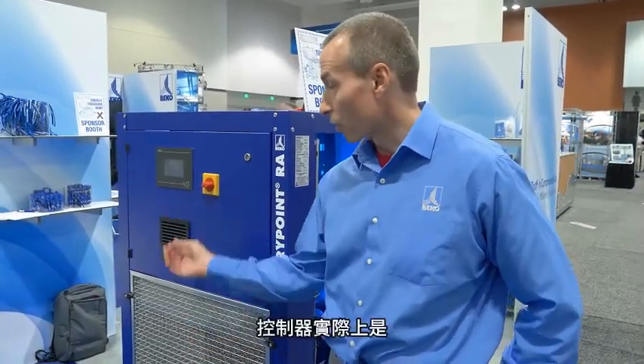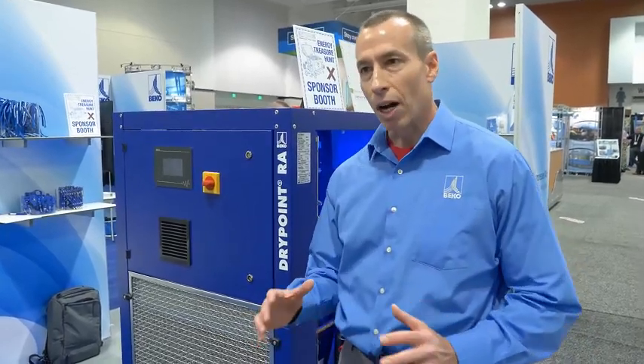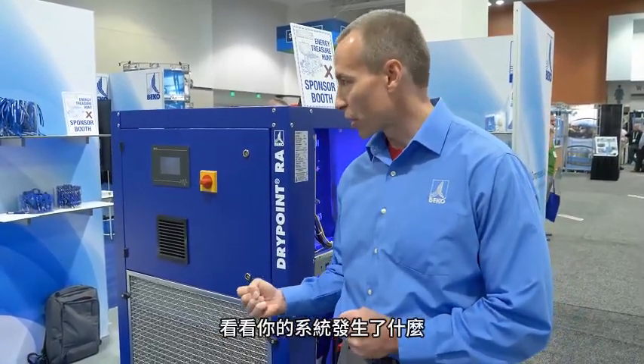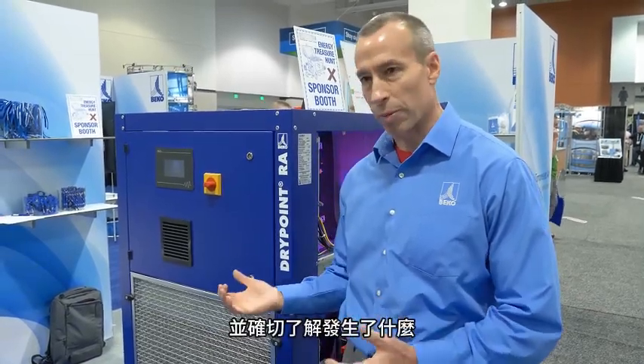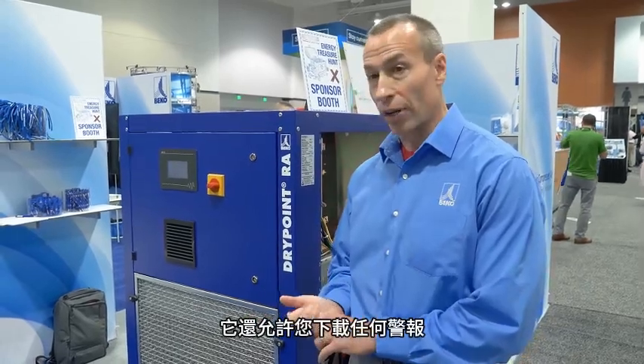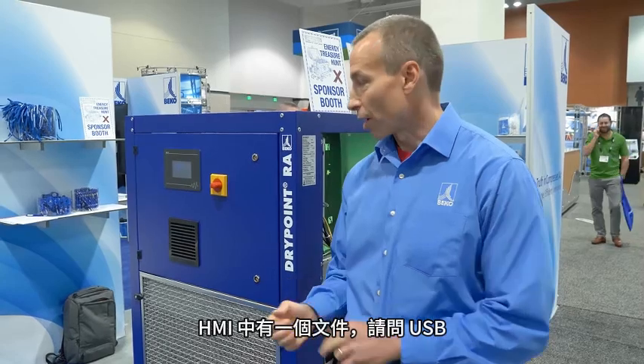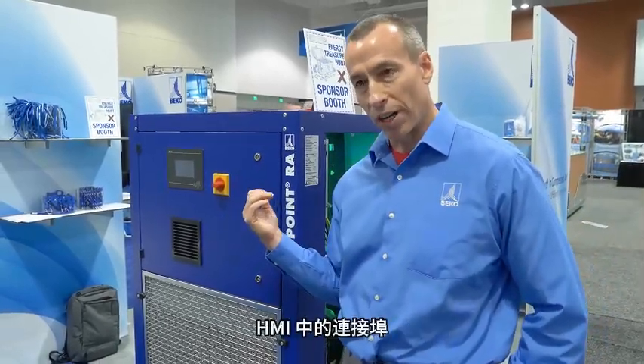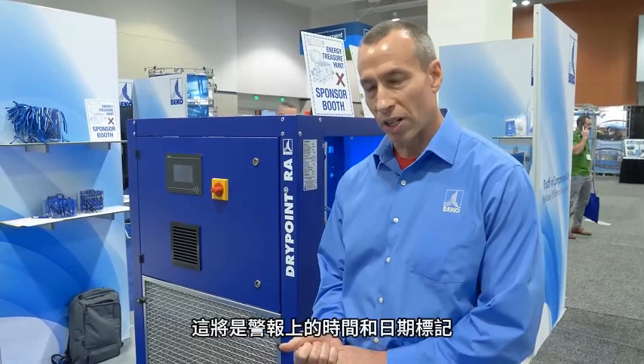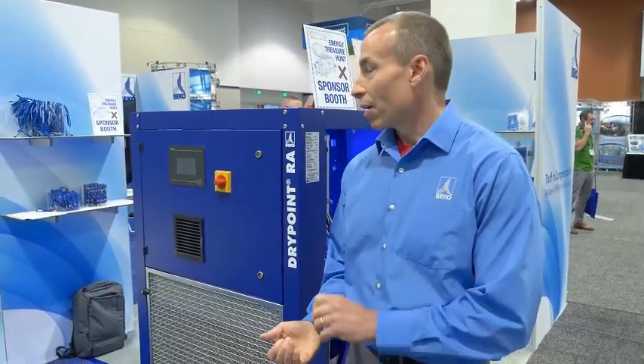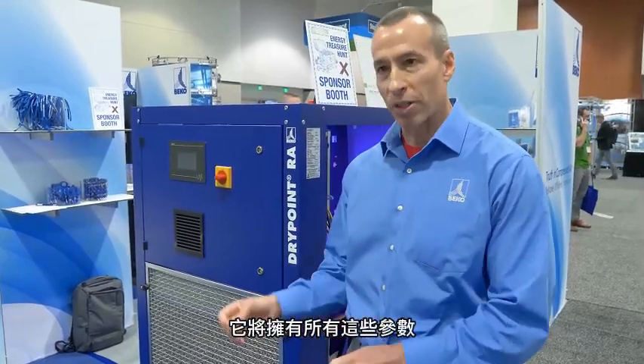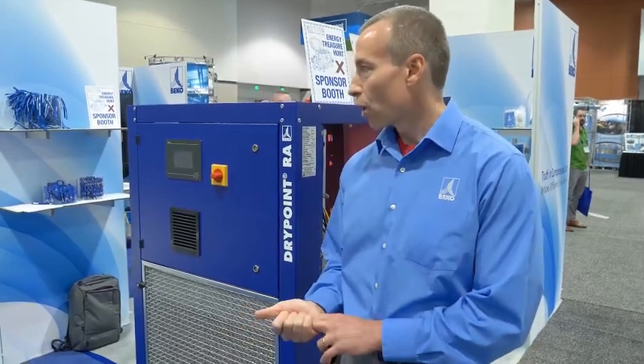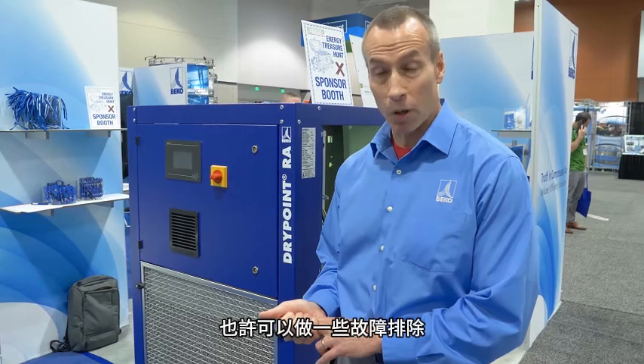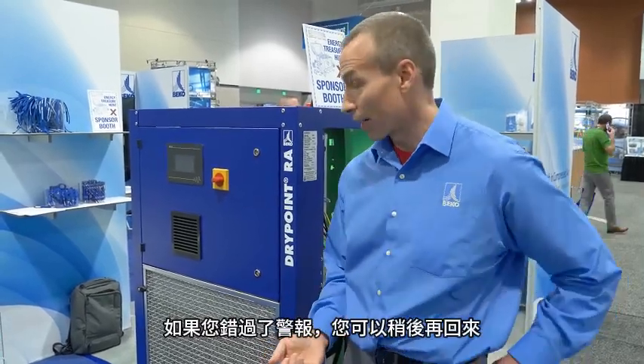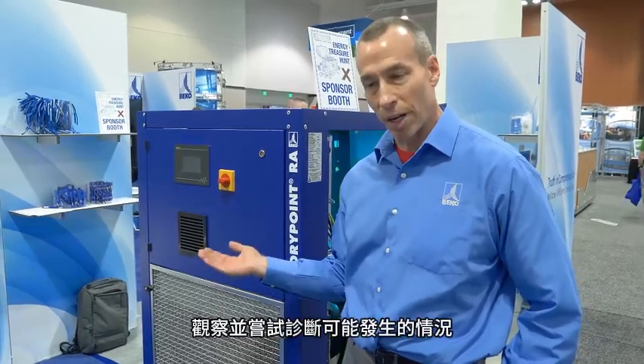What the dryer also does in this controller is that it actually keeps the last 60 minutes of operation as a running total. So if you ever want to go and look at what's happening in your system, you can check the last hour of operation of the dryer and see exactly what's been happening. It also allows you to download any alarms you may experience. There's a USB port in the HMI, which will allow you to download a TXT or a text file. That text file will contain what type of alarm it was. It'll be a time and date stamp on the alarm, and it will also have the hour before the alarm occurred. It'll have all those parameters, the temperatures and pressures that were going on, so that you can actually analyze what type of alarm it was and what caused the alarm, and maybe do some troubleshooting even after the fact. If you missed the alarm, you can come back later and you can actually take a look and see and try to diagnose what might have happened.